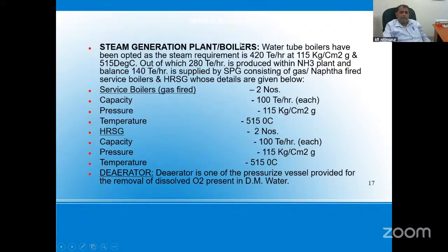We require only 130 to 140 ton per hour of steam to run the equipment in the offsite plant and in the urea plant. To meet such requirement, we have 2 service boilers. Full detailed description is here. Capacity 100 ton per hour each. Generating pressure 115 kg per cm square. Temperature 515 degrees Celsius.